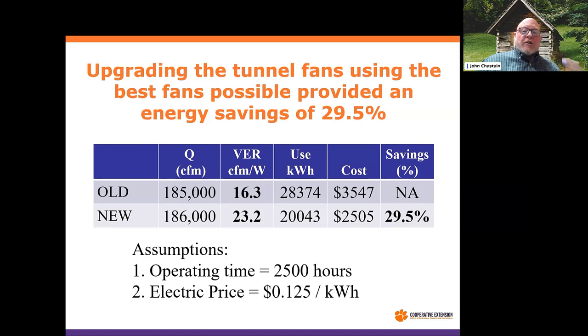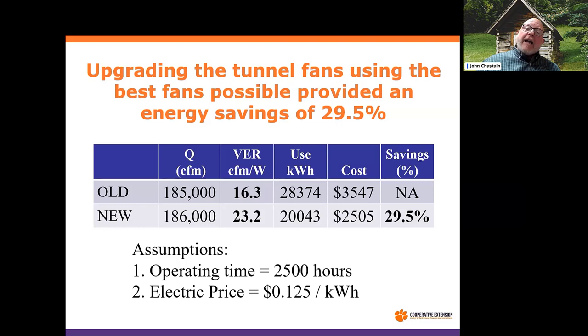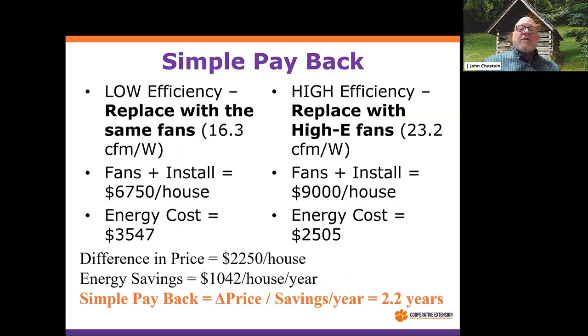The choice was: replace with old-style fans at VER 16.3 — similar to what they already had — or buy the most efficient fans that provide essentially the same airflow with a VER of 23.2. That higher VER is what delivered the 29% savings projection. However, the fan dealer had fans in stock from the same brand that only just met or slightly exceeded the ASABE number of 17.6, so we evaluated that option as well.